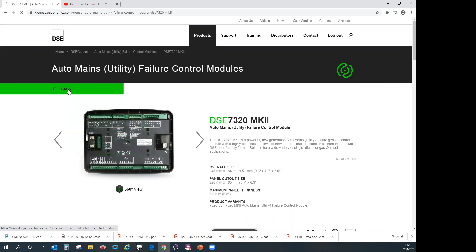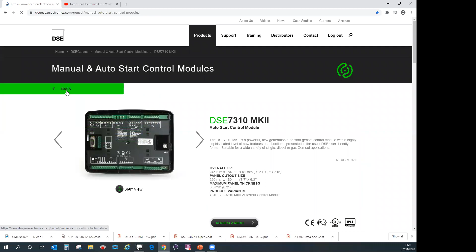If we scroll around to the back here and look at the back of this one, we've got voltage monitoring for V1, which is the generator, and then V2, which is the actual building mains, the mains monitor as well. So if the voltage drops off here, the generator will automatically start. If we go back to the 10 and go to the reverse of the 10, we can see on this one, it's very similar looking, but there's no monitoring on V2, there's no voltage monitoring.